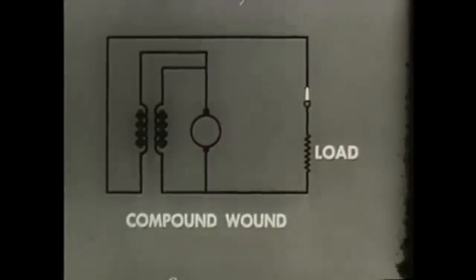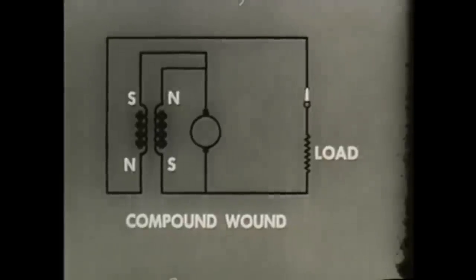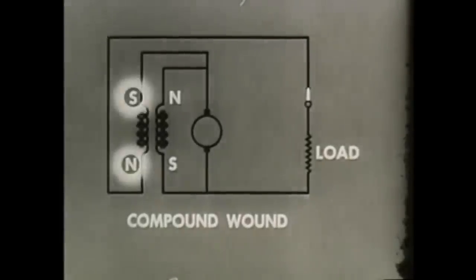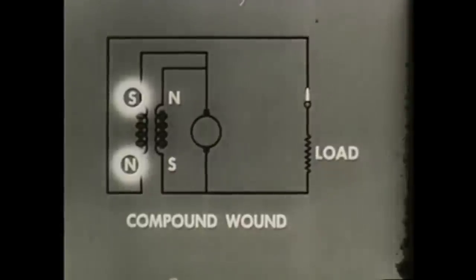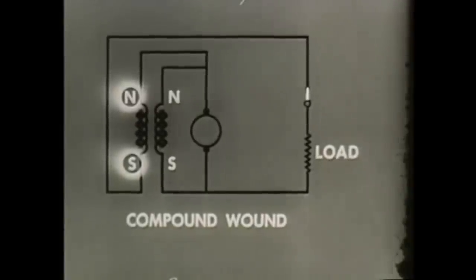By changing the armature winding, a compound-wound generator results, which combines the best features of both types, the series and the shunt-wound generator. When windings are arranged so that magnetic fields oppose each other, it becomes in effect a series generator. This is used only where constant current is the prime requirement, such as in arc welding. By changing the magnetic polarity of one of the fields, the field windings aid one another. As a result, this compound-wound generator has good voltage and fair current regulation.